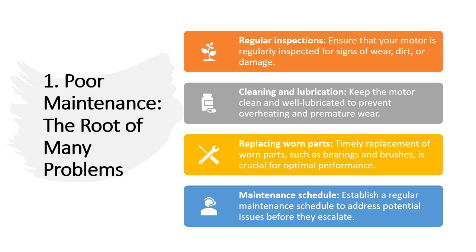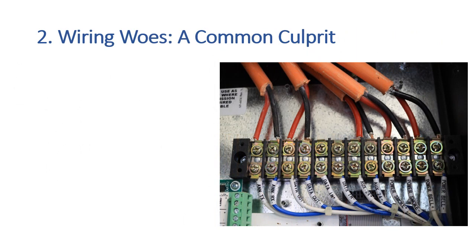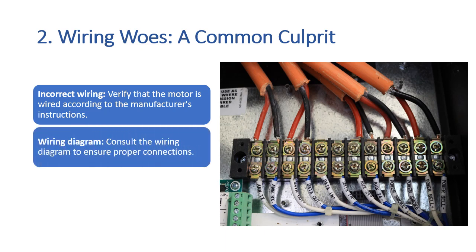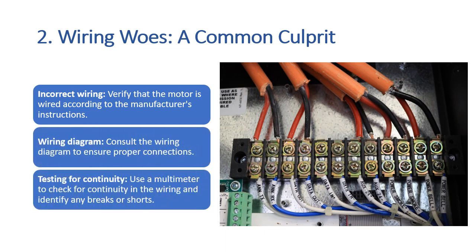2. Wiring woes, a common culprit. Incorrect wiring: verify that the motor is wired according to the manufacturer's instructions. Wiring diagram: consult the wiring diagram to ensure proper connections. Testing for continuity: use a multimeter to check for continuity in the wiring and identify any breaks or shorts.